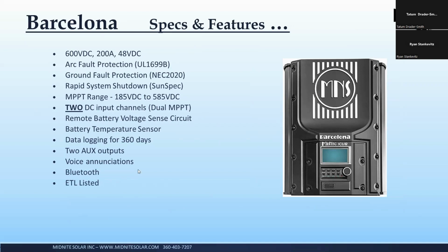The other thing we did with the new products is we now have a ground fault device that is optional that will allow you to solidly ground the negative. Now, I'm not 100% sure where you guys are on code up there in Canada, but I know here in the States, we've got this thing called reference grounded and solidly grounded. The way the code here words it is any conductor in the system that is not solidly grounded is considered current carrying. So if you're used to using the Classic, for example, or the old Outback circuit breakers for ground fault, or one of our circuit breakers for ground fault, that's considered reference ground.